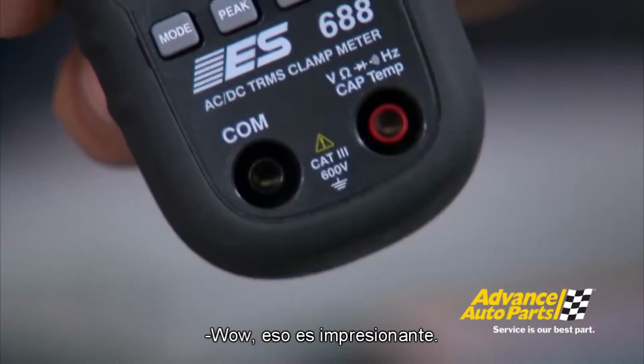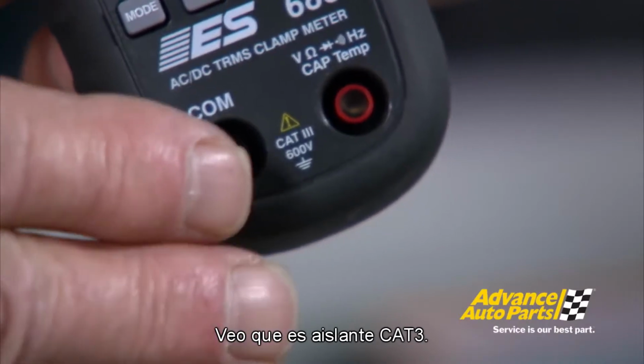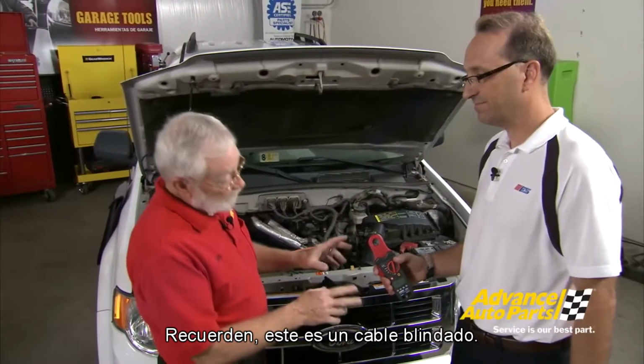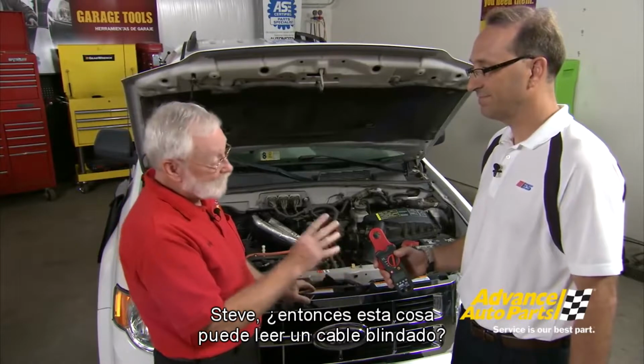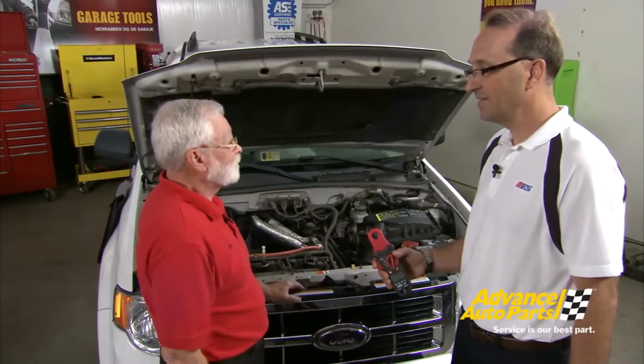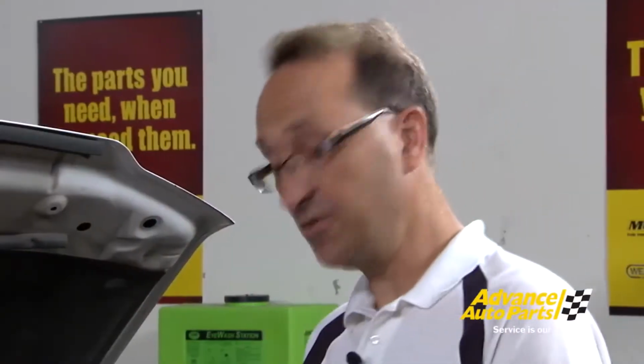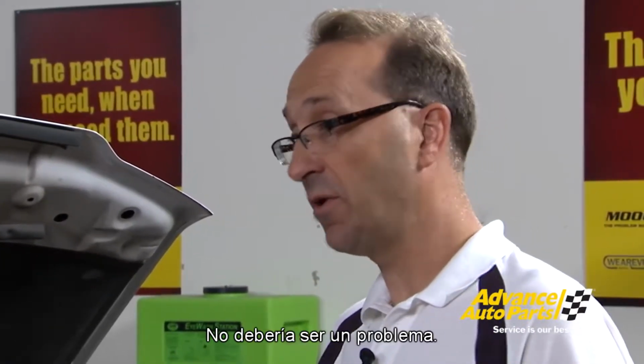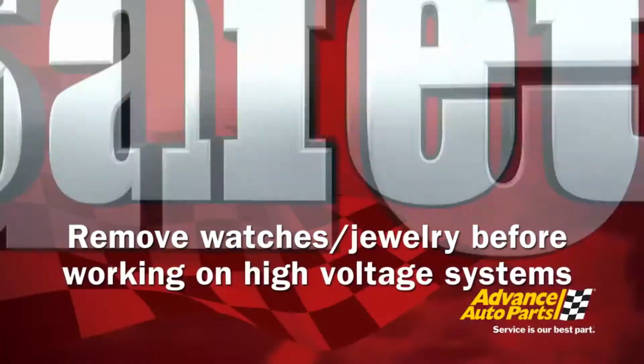Wow, that's impressive. And I see it's Cat 3 insulated. Remember, this is a shielded cable now, Steve. So this thing can read a shielded cable? Yes, it's a Hall effect sensor in here, so it should pick up the electromagnetic field going through that wire. It should not be a problem. Yeah, definitely what it's designed to do.